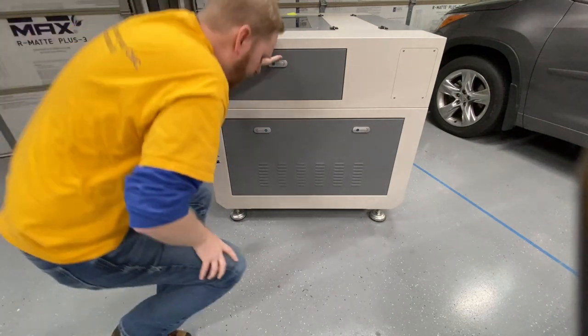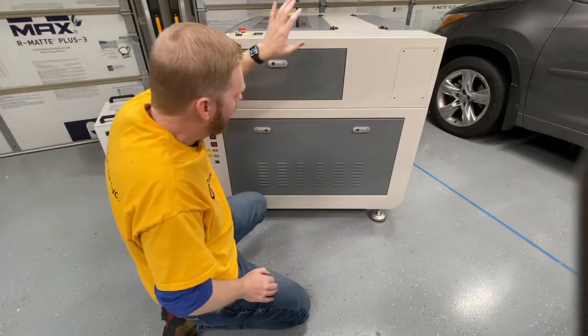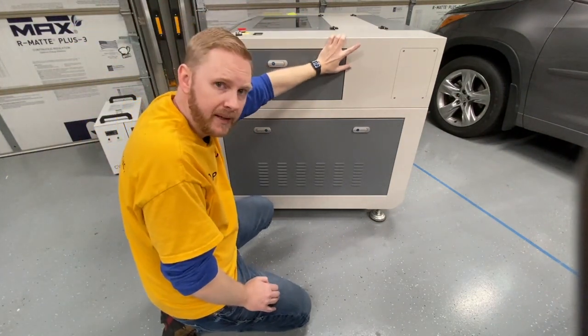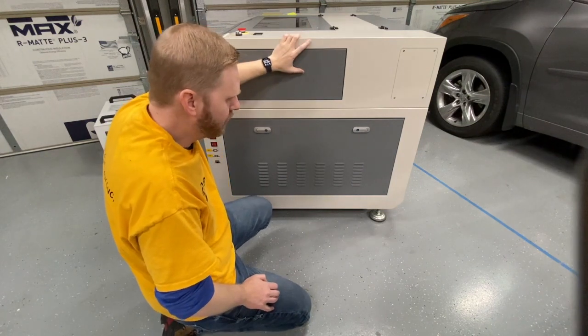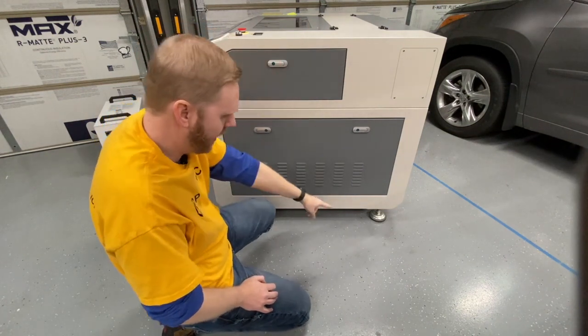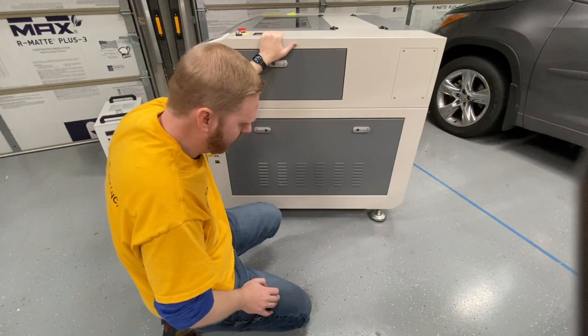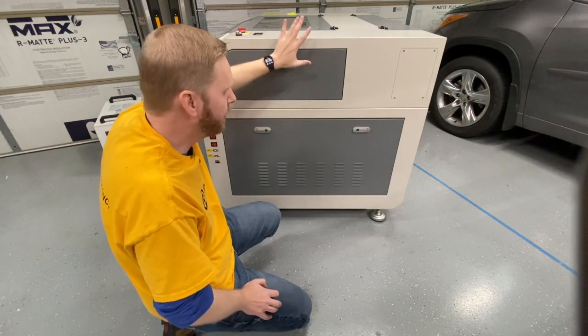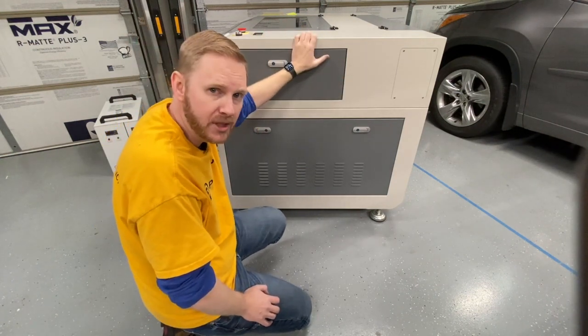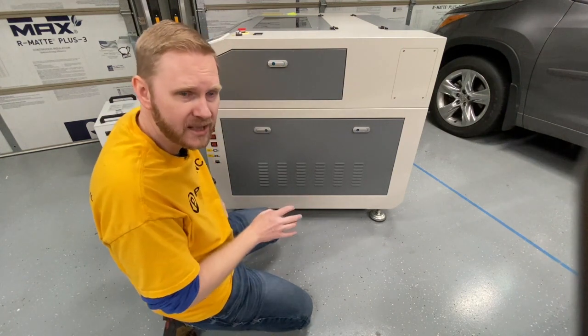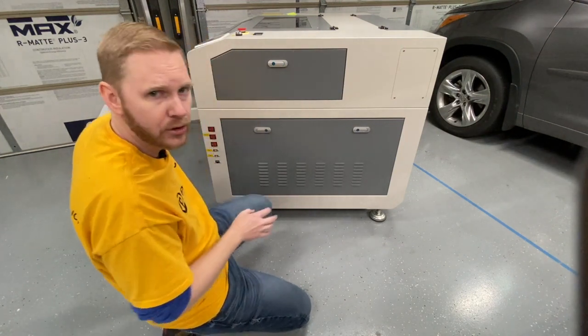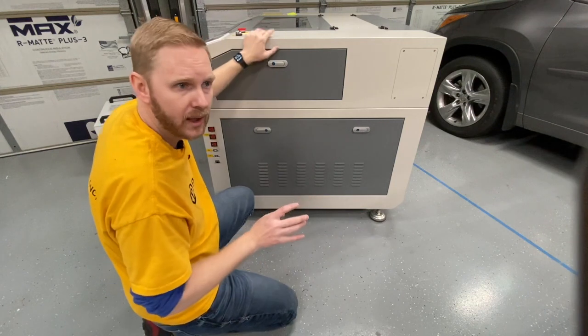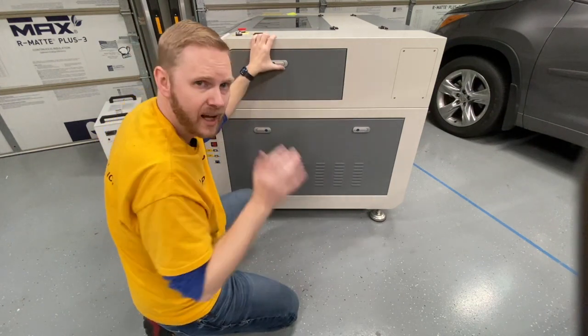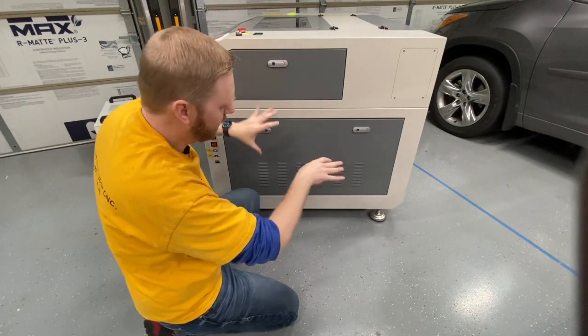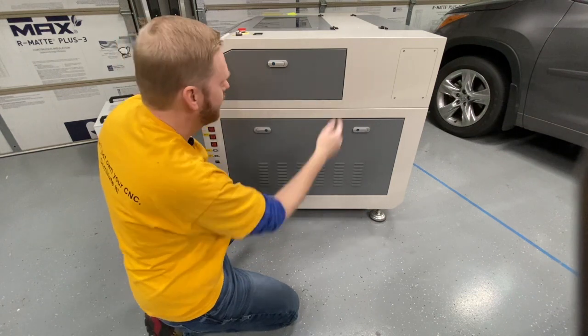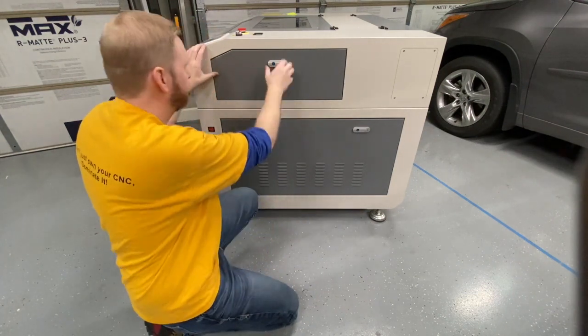Just so you know, I haven't installed the tube yet. I'm waiting to do that until I actually level and place the static feet on my machine. I don't want to be moving the machine around while the tube is in position, since I don't want anything to become discharged or out of alignment. So we'll wait until the machine is completely in place, then install the tube, and we'll do a video on that too.